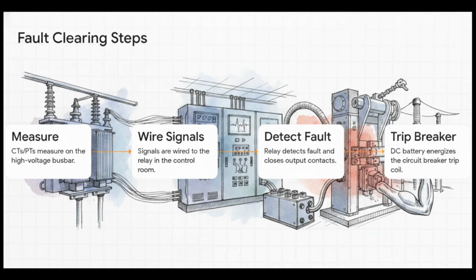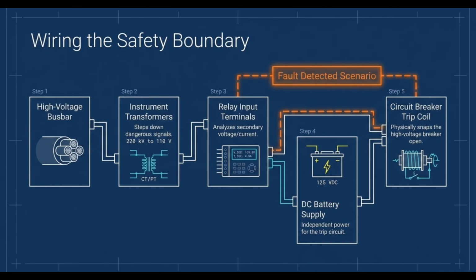So how does the system actually react when something goes wrong? It follows a very precise fault-clearing sequence. First, sensor transformers out on the high-voltage busbar measure the activity. Second, those step-down signals are wired safely over to the relay in the control room. Third, if the relay detects a fault, it instantly closes its output contacts.